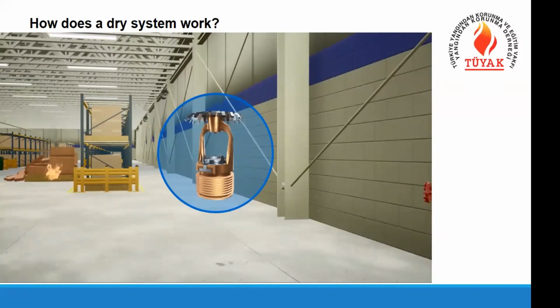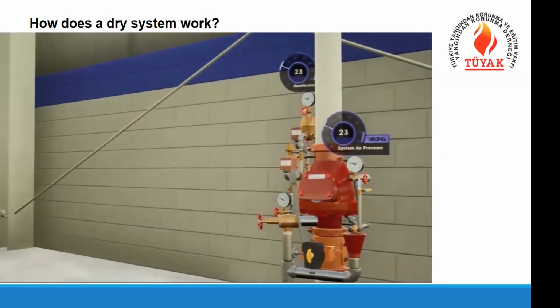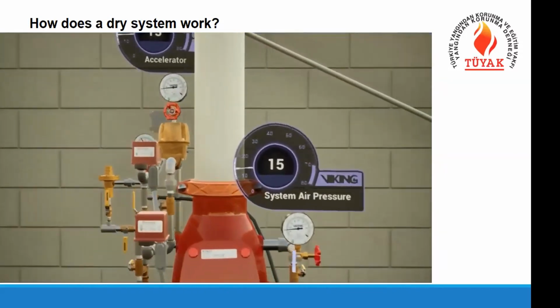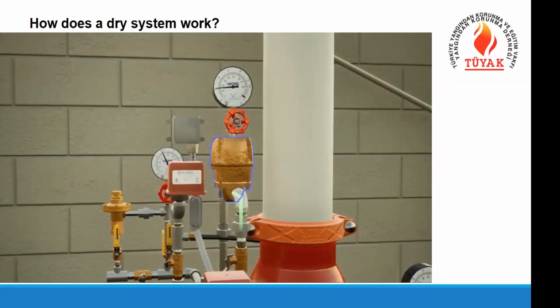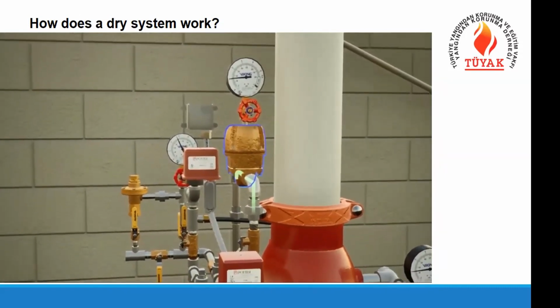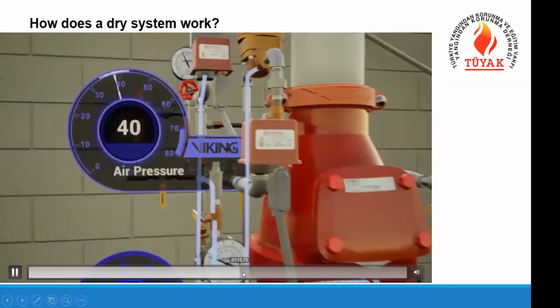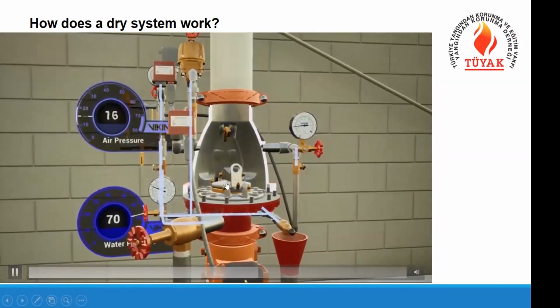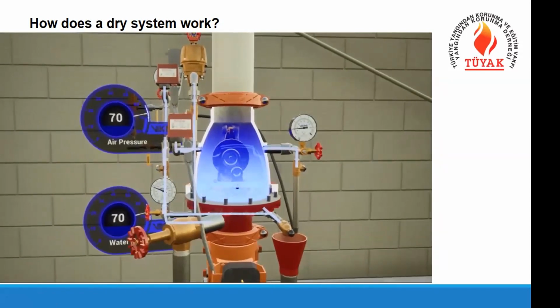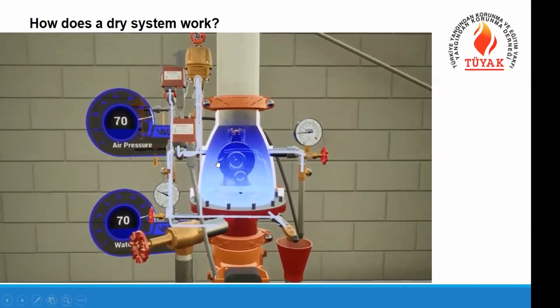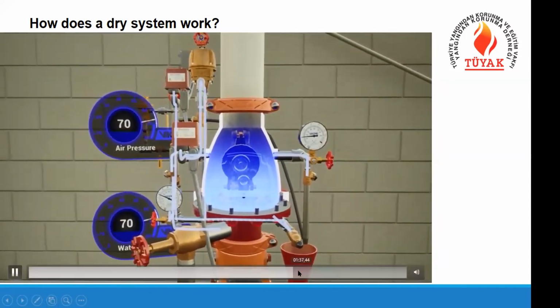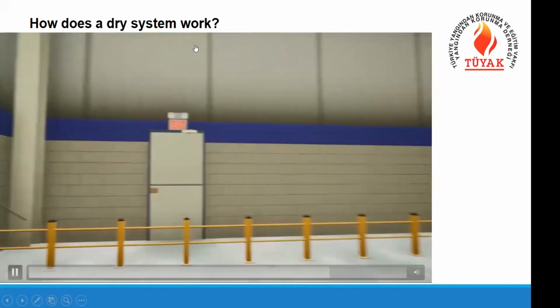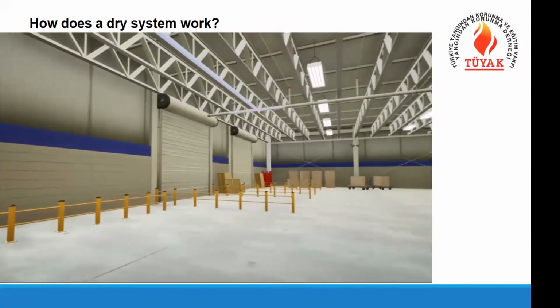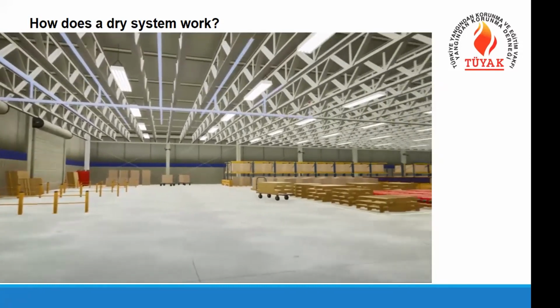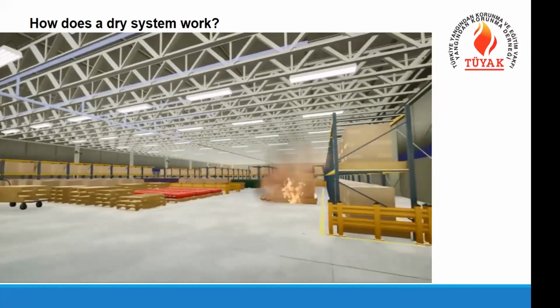So the sprinkler activated. After the activation, the air inside the pipes escapes from the pipe, so the air pressure is reducing. When the pressure drops, the valve opens. The clapper inside the valve body opens and releases the water into the pipe. As you see on the ceiling, the water passes through all the pipes and goes to the open sprinkler, and just above the fire, it discharges the water.